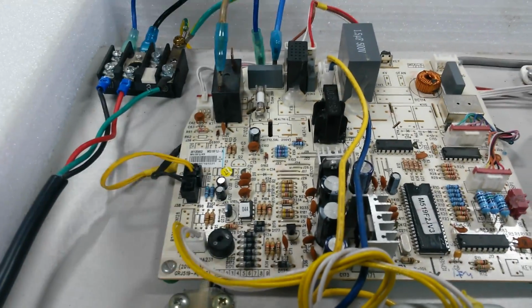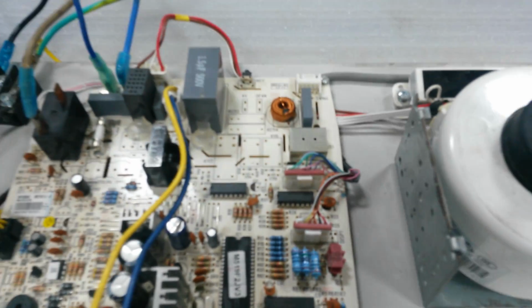But before it can take a decision to start the compressor, it will ask for feedback from the coil sensor as well. If the coil sensor says there is no frost on the evaporator, only then will my microprocessor wait for the final call from the memory IC. The memory IC will show whether there is a 3-minute delay or not. If that 3-minute delay is also cleared, immediately my compressor will start.